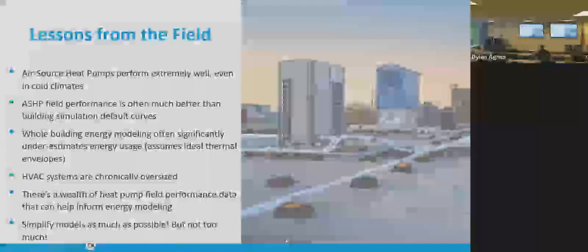Air source heat pump field performance is often much better than what building simulation curves have built into them. It's oftentimes a little worse than what the manufacturers produce in the lab. But if you use the standard curves, they're oftentimes significantly going to underestimate performance.